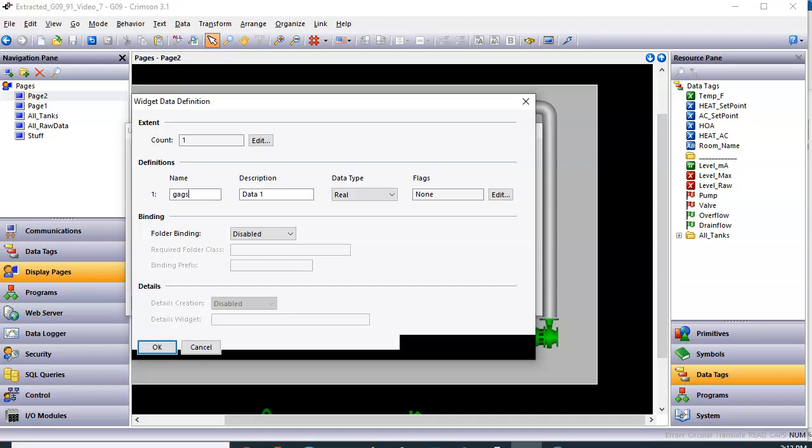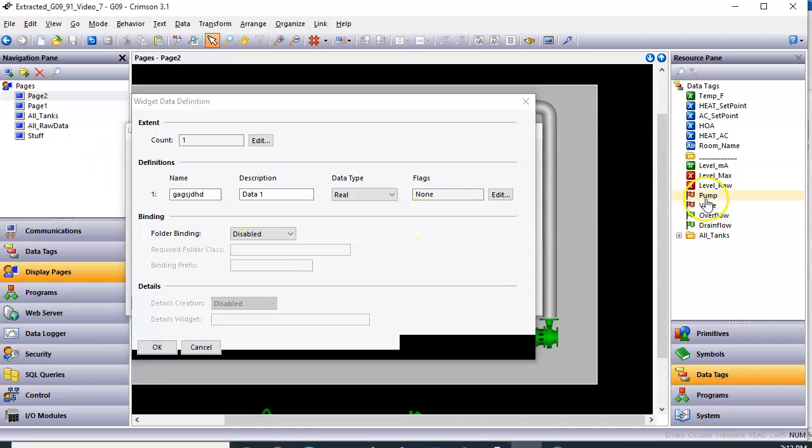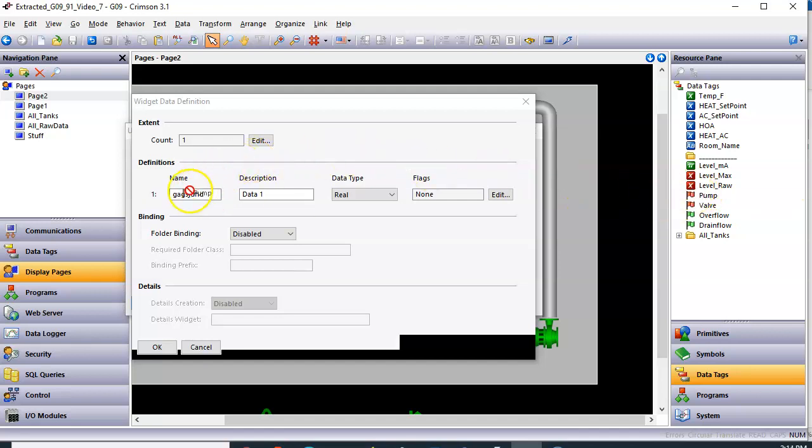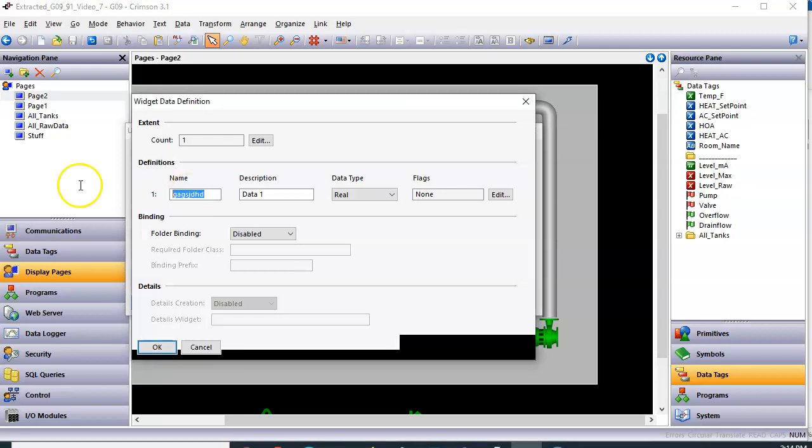A lot of people in class will say, well, why don't I just drag this guy? You know, I've been talking about dragging and dropping. Why don't I just drag it right here? Well, if you notice, as I try to do this, Crimson at the widget definition section doesn't let you do that because if you did, you just took this graphic and you hard coded it or hard welded it to that tag level. So that's why it doesn't let you do that. So I'm going to manually type the word pump here.